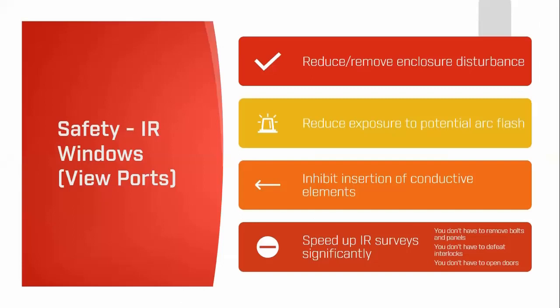Talking about windows: a faulty connection can be an explosion waiting to happen, and the more we disturb its environment, the greater the chance of triggering an event. We've all seen photos or videos of arc flash events — even steel covers won't always protect someone nearby, but they're better than no cover at all. With an infrared window, it won't totally protect you either, but it's better than removing the entire panel. IR windows make the thermographer's job easier — just open the window cover, shoot, and close it. No bolts to remove, no safety interlocks to defeat, and the technician may be able to wear a reduced level of PPE.